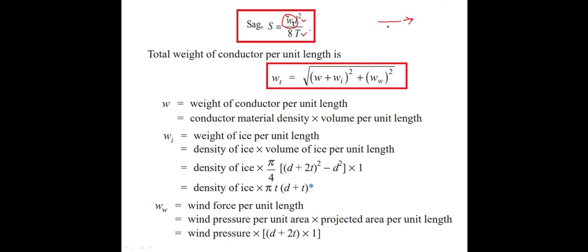This comes from the SAG diagram — wind force is horizontal, weight of conductor and weight of ice are in the downward direction. Taking the resultant using Pythagoras theorem gives this equation. All weights must be in kg per meter. Weight of the conductor is given directly in kg per meter. Only Wi and Ww need to be found using formulas.